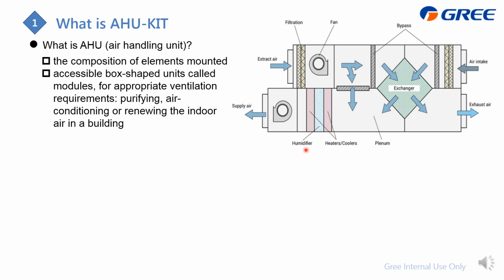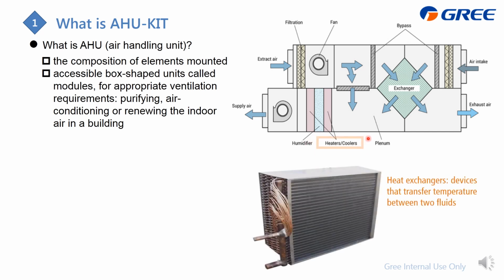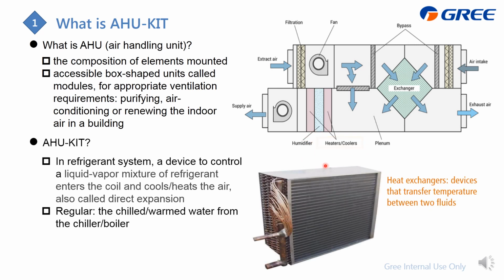For the AHU kit, focus on this part: we offer the refrigerant to the heaters or coolers. It is just the heat exchanger, making heat exchange between the air and the inside fluid. For the AHU kit, we just offer the refrigerant within the refrigerant system. The AHU kit is a device to control the liquid and vapor mixture of the refrigerant entering these coils to make heat exchange, also called direct expansion. This direct expansion is compared with the regular chilled or warm water from a chiller or boiler.